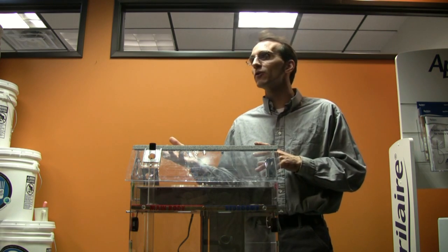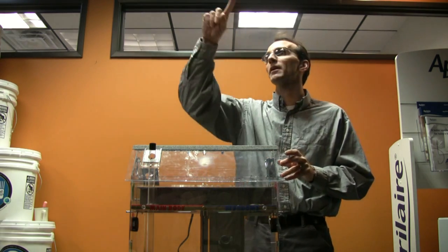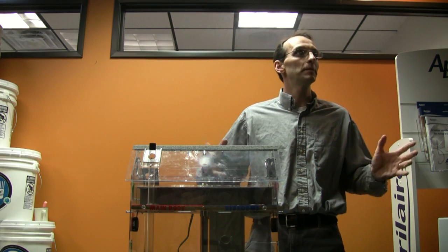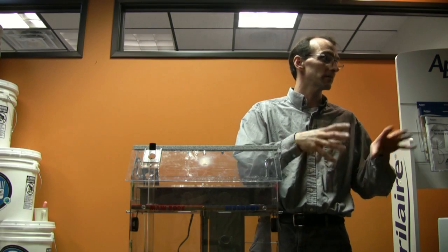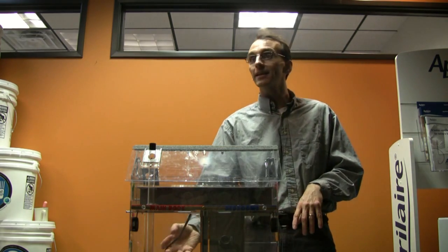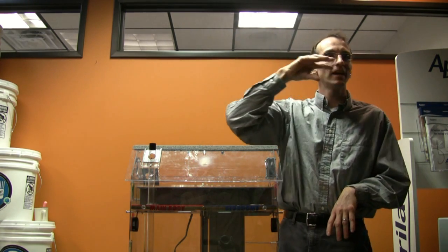And we've done studies at homes where we put air monitors in, and you can see the carbon monoxide levels go like this in the home when people get home. It's especially true for attached garages. People get home, they park the car, there's carbon monoxide from the car exhaust. They come in, the furnace goes on, there's a leaky return air. It sucks all the car exhaust from their garage and dumps it into their house. And then you get this big spike of carbon monoxide in the house.